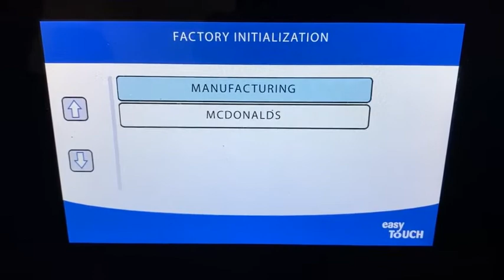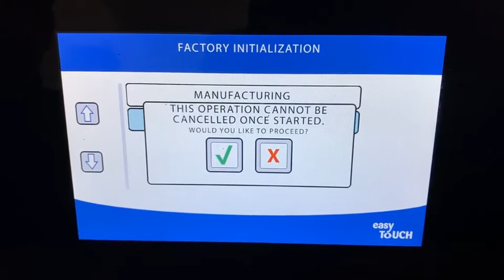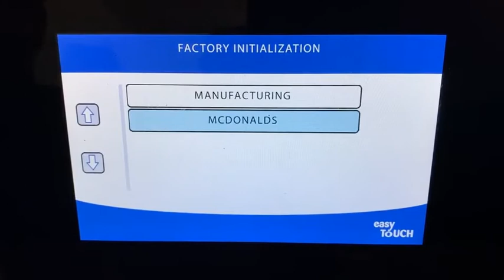Once the unit's rebooted, you're going to come to this factory initialization. Depending on what grill you're on depends on what options you're going to have. On a McDonald's grill, you'll have 2 options: manufacturing or McDonald's. If you press manufacturing, it will allow you to use the controller normally until you reset the power. When you reset the power, it will take you back to this screen and lose all of the settings you've put on, so you should pick McDonald's. If this was a general market grill, it would say manufacturing and general market. Or if it was Chick-fil-A, it would say manufacturing and Chick-fil-A. Once you've pressed it, you can't redo it without starting the cycle again.